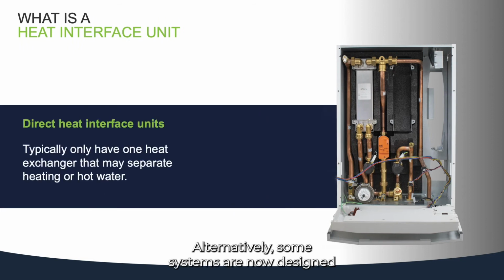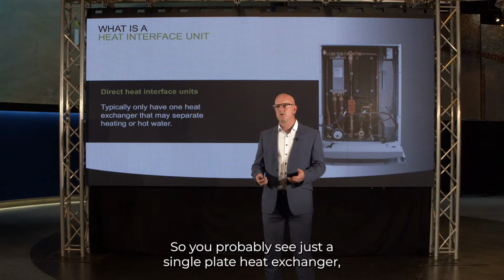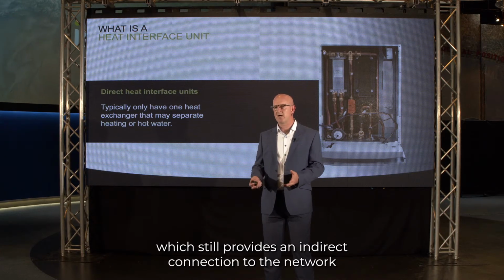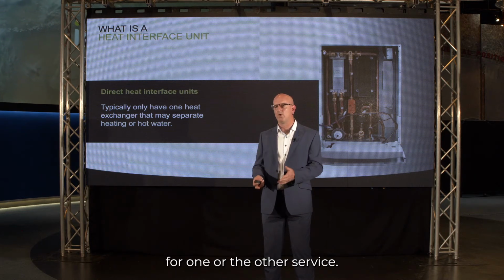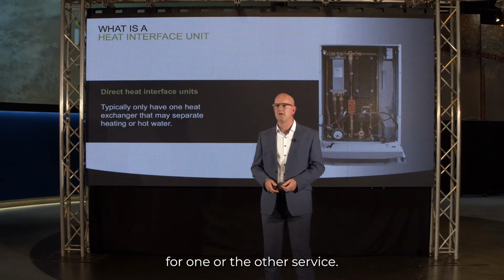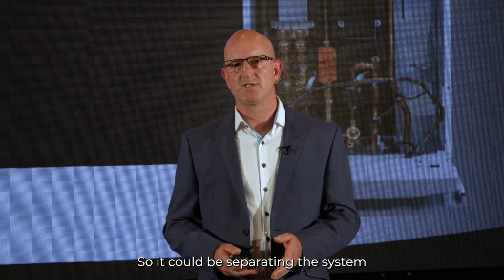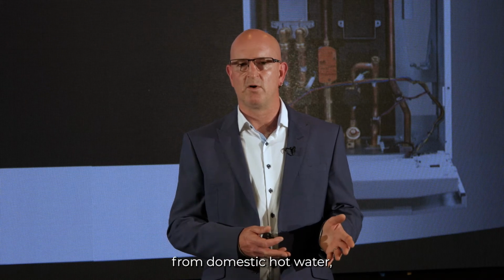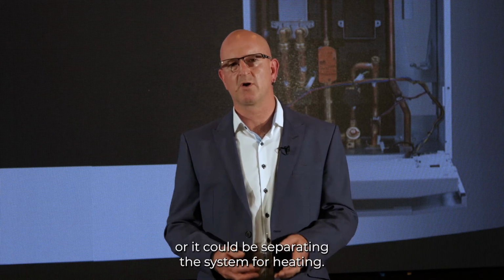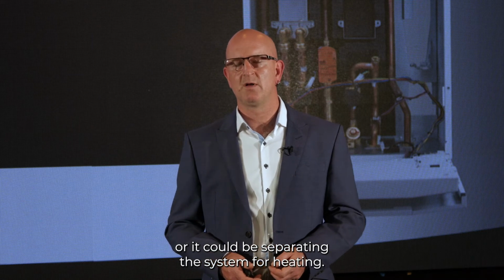Alternatively, some systems are now designed to have a direct connection. So you probably see just a single plate heat exchanger which still provides an indirect connection to the network for one or the other service. So it could be separating the system from domestic hot water, or it could be separating the system for heating.